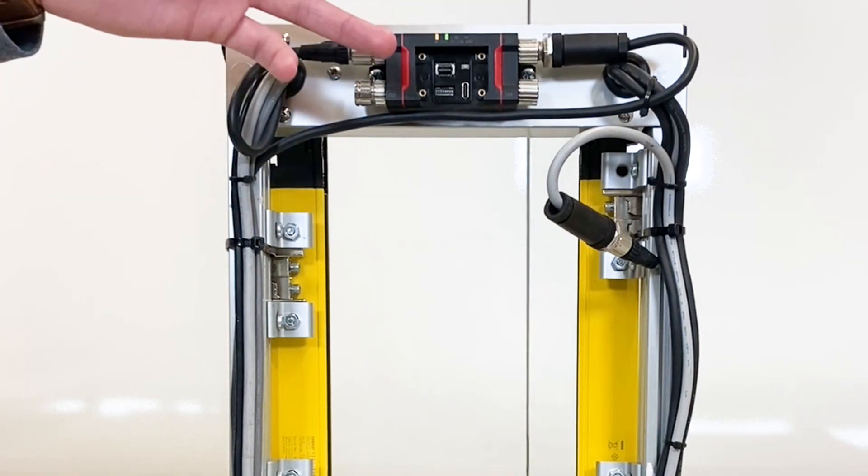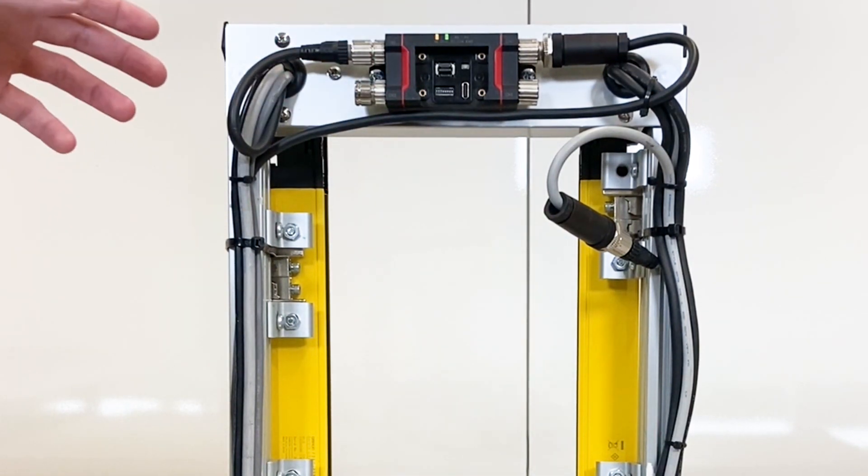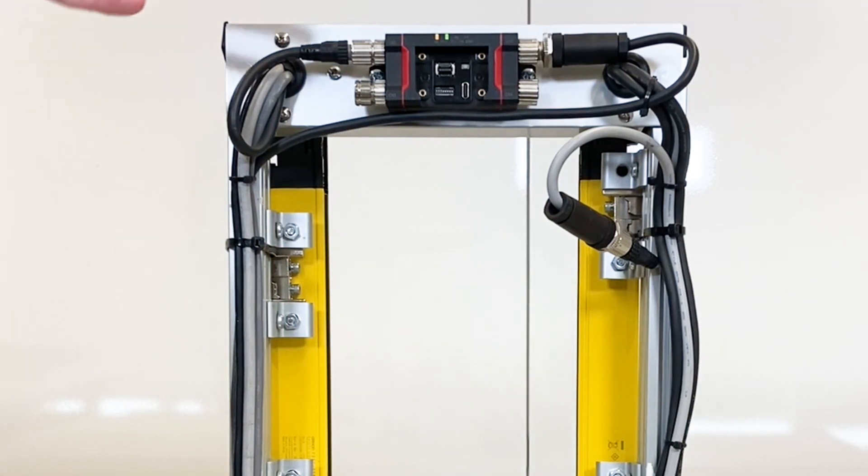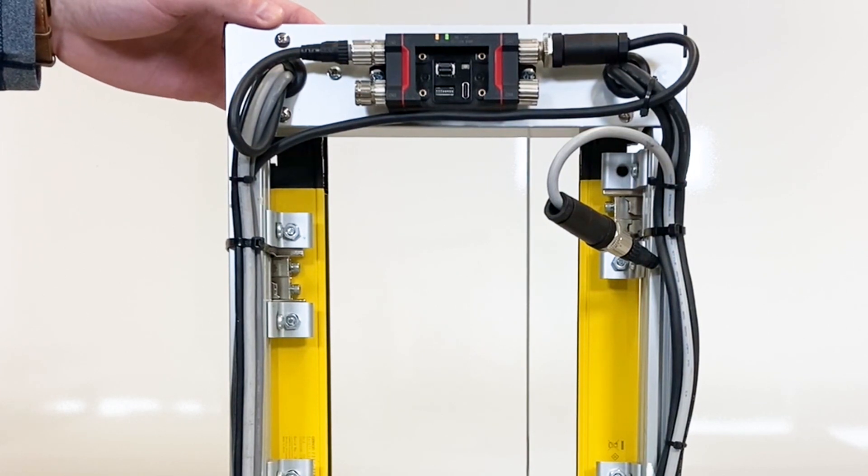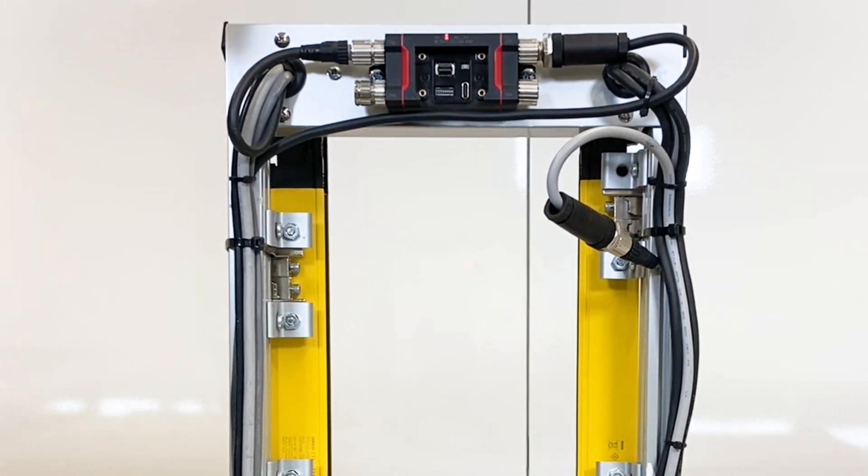If you did receive a red error light, what you want to do is power your system off and check the wiring of your system. But in this state, since everything is good to go, what we want to do is power the system back off, wait a couple seconds, and then power back on again. Now your safety light curtain is good to go.